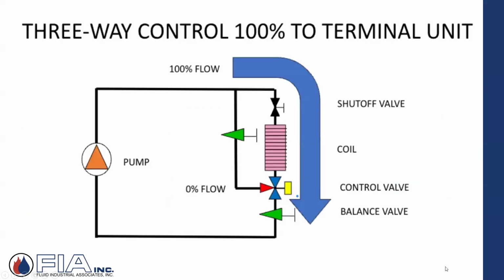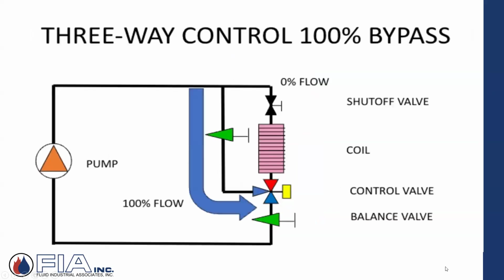Real quickly, this is just kind of a highlight, or an exploded view, of what's going on with that bypass and that three-way valve. And most likely it was a modulating valve, which would mean what? What's the modulating valve mean as opposed to, say, a two-position three-way valve? Two-position would be, in this case, 100% open to the coil, so blue to blue, red indicating closed, so all the flow's going through my coil. And if I went to the extreme the other way, the red is closed from the outlet of the terminal, so I have no flow through the terminal. All of it's going through my bypass pipe. Here's my balance valve to simulate that terminal pressure drop.